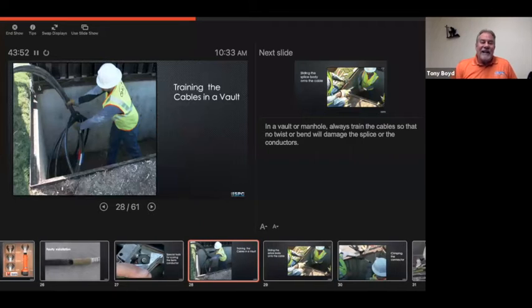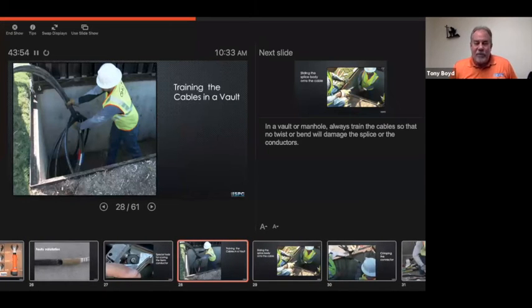All right, training the cables in a vault. It's always important, especially in a vault, large vault or small vault. It's important to train the cables, because when they come in from one way or the other, and as you can see, we had 3 phases that came in from the left side, 3 phases that came in from the right side. The important thing about training these cables in a vault is you may have one cable that has come in twisted this way, one cable that has come in and twisted this way.